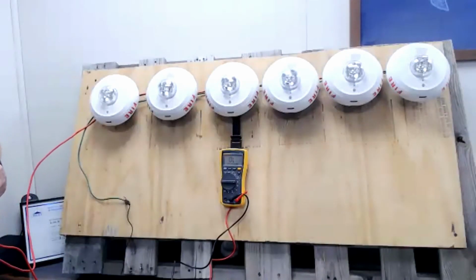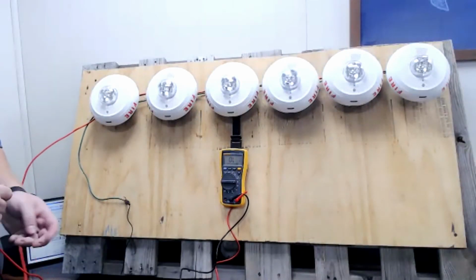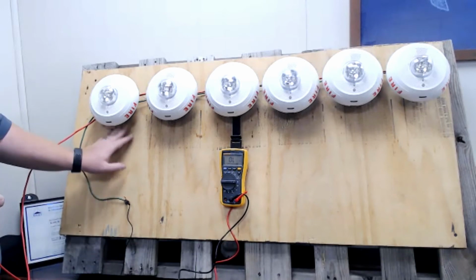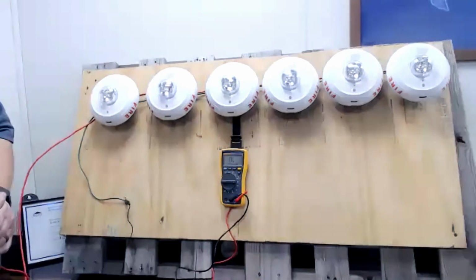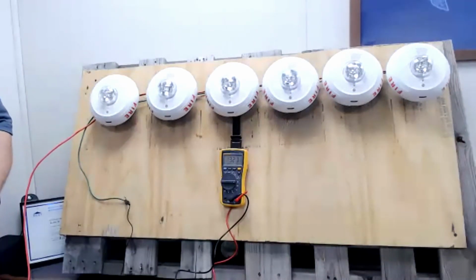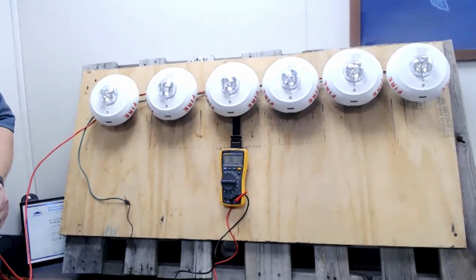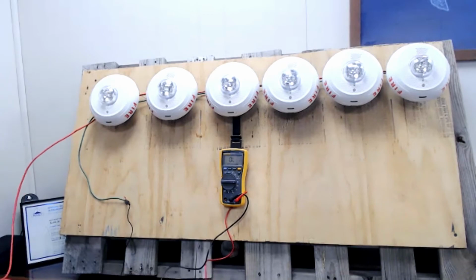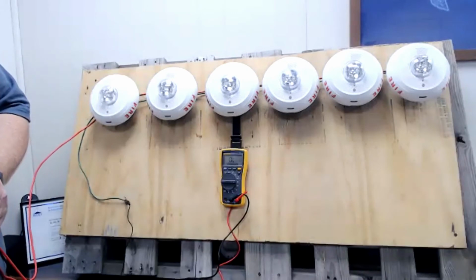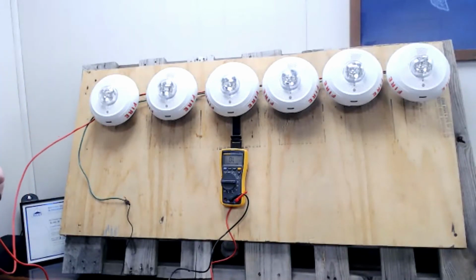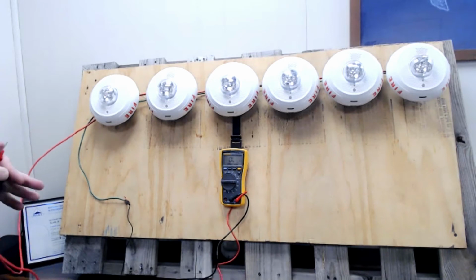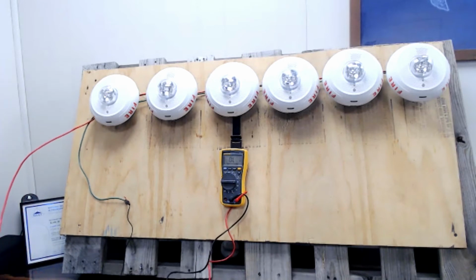And that lets us skip to checking for the very last thing. Now we're going to look for a ground fault. So again, I've created my ground reference here. I can use any of these back boxes as a good ground reference. Some of the other things we talked about in last week's lesson are any kind of bare metal around the building, conduit, water pipes, things like that. They're great ground references. The metal casings on air handler units, if you're working in the ceiling and you have an air handler right above you, you can touch your meter lead to the bottom of that drip tray. That's all grounded.